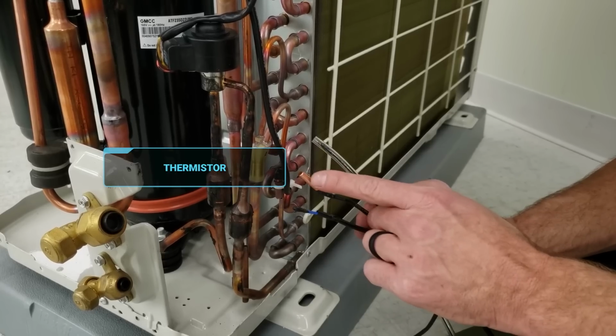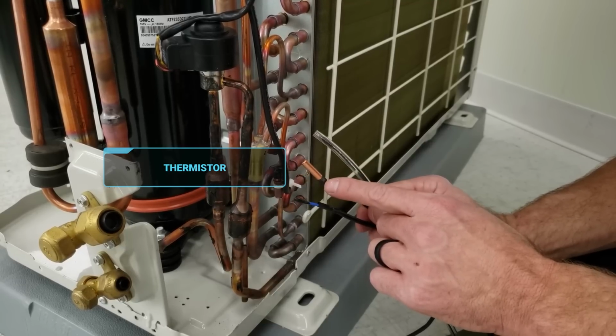But another thing is the thermistors, and a lot of times people ignore those and they get out of calibration. You have a tube thermistor or a bead thermistor, and with the system powered down, you can check the electrical resistance values of that and compare that to the temperature. So a lot of times I'll take a temperature meter, I'll tape that temperature sensor to the bead or the tube to make sure that they're at the same temperature, and I'll use the manufacturer's chart while measuring electrical resistance and making sure it's very close. Because if you're, I forget what it is, maybe 7% off, you're talking like 3 to 5 degrees off, and the whole system's parameters is based on that. And so you're totally jacked up at that point, with your efficiency. So that's a huge deal, and you have multiple thermistors to check.